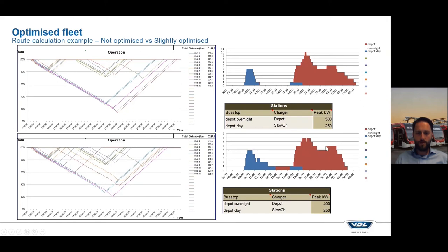And you can optimize that further. As you see, there is already a decrease to five just at 11 o'clock. And then after two o'clock, more or less all the buses stop charging because they are full. So this peak, you could also move to the back. And then maybe you need only five chargers. That's something I didn't do in this slightly optimized version, because there are a lot of different ways how to achieve this with more advanced software that the customer uses on scheduling their buses. It's just to show you the two options that I did: changing buses to reduce the driving time and delaying charging time.